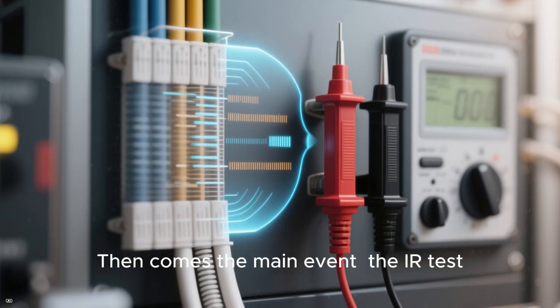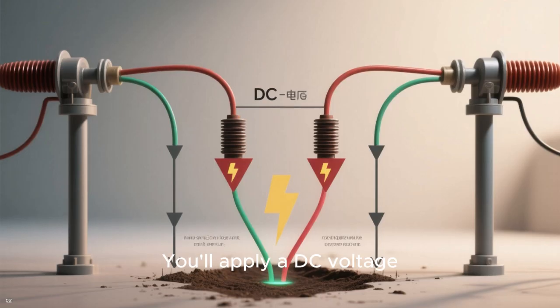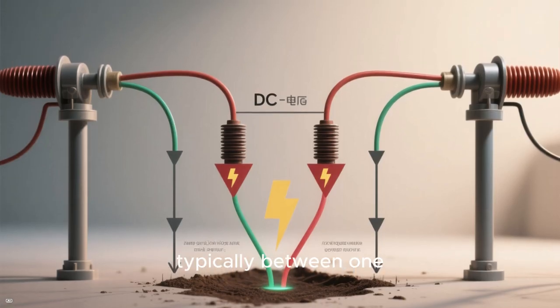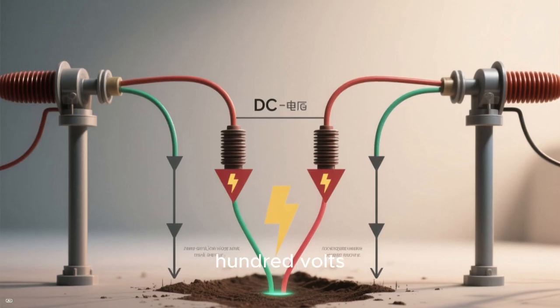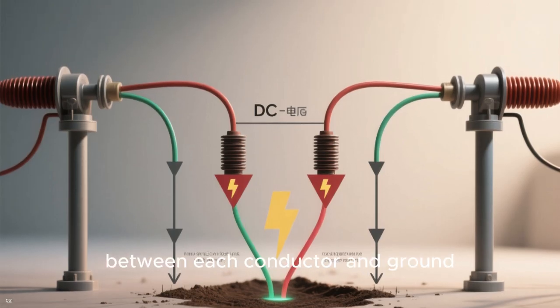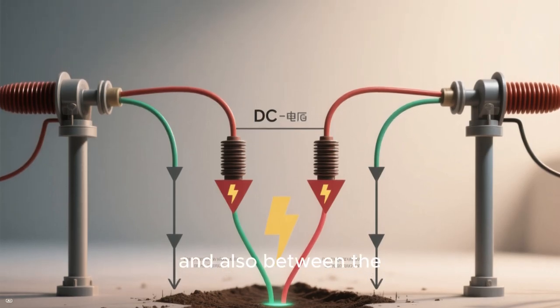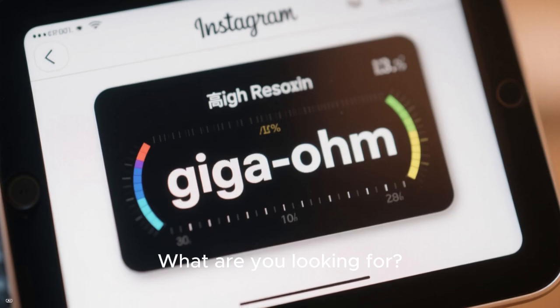Then comes the main event, the IR test. You'll apply a DC voltage, typically between 1000 to 2500 volts, between each conductor and ground, and also between the conductors themselves. What are you looking for?